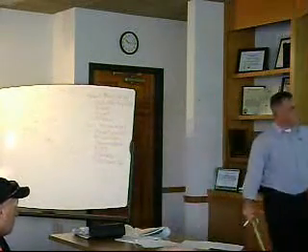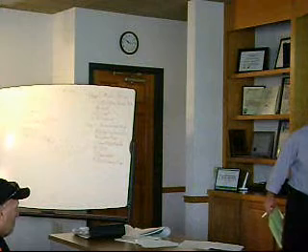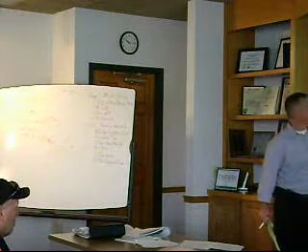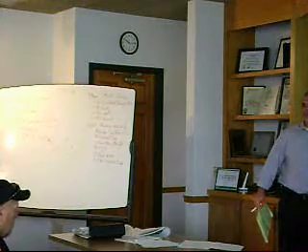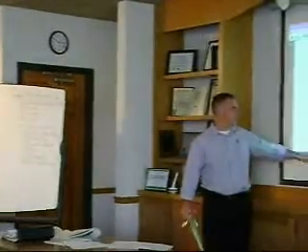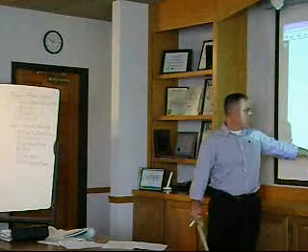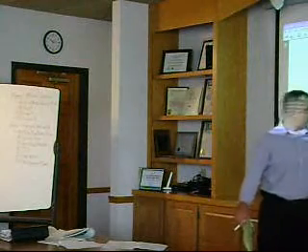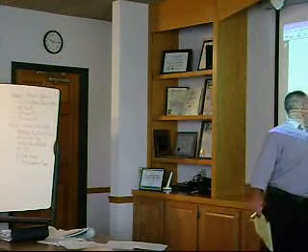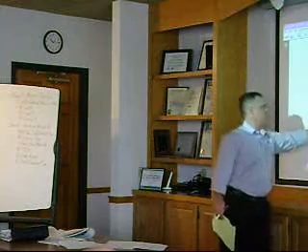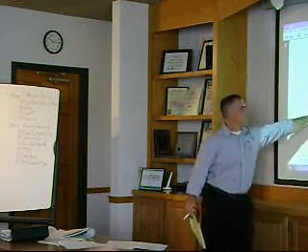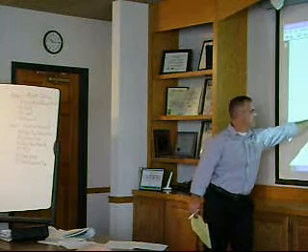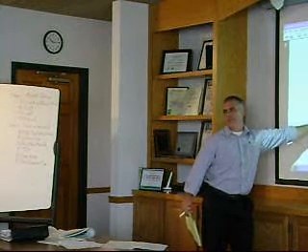What he tells you here is he gives you your orifice spacing and your lateral length in feet so that you can determine what size lateral you need to use to feed this stuff. So, for example, if my hole spacing was 2 feet, my maximum lateral length with 1.5 pipe is at 37 or so feet.